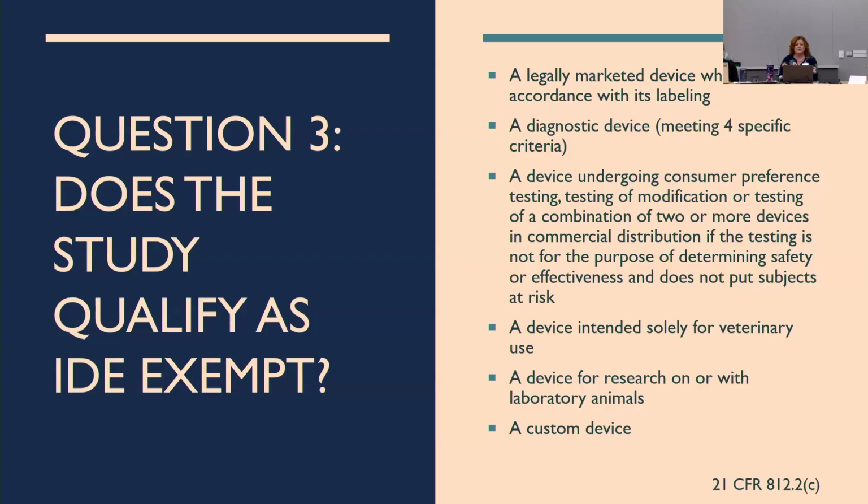Or if it's a device undergoing consumer preference testing or testing modification, or a combination of 2 commercial devices already in distribution, it can be exempt then. And then the last 3 here are custom device, research with lab animals, or solely for veterinary use as well. So those are the IDE exemption criteria.